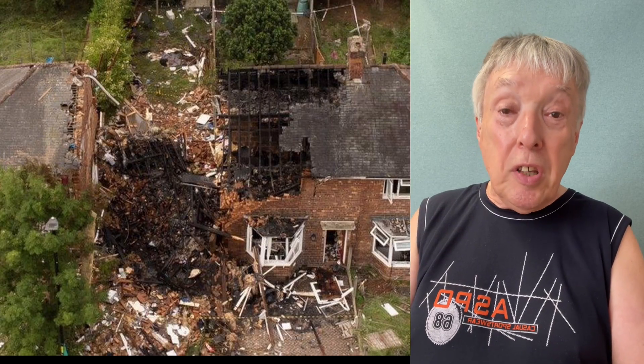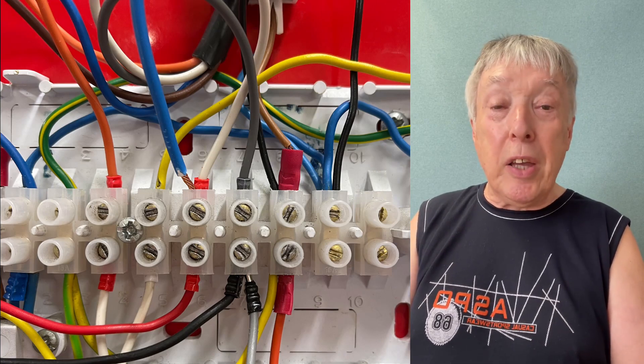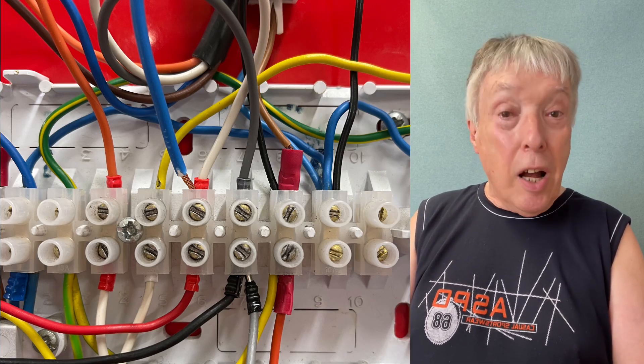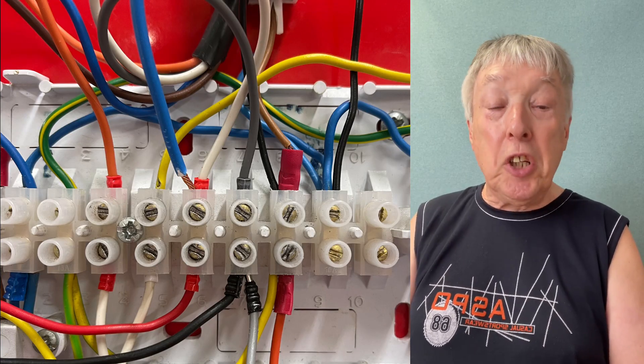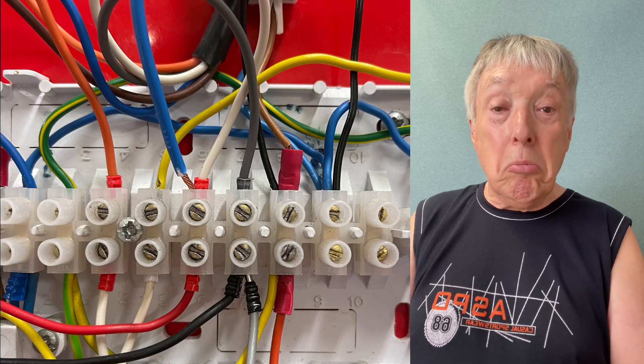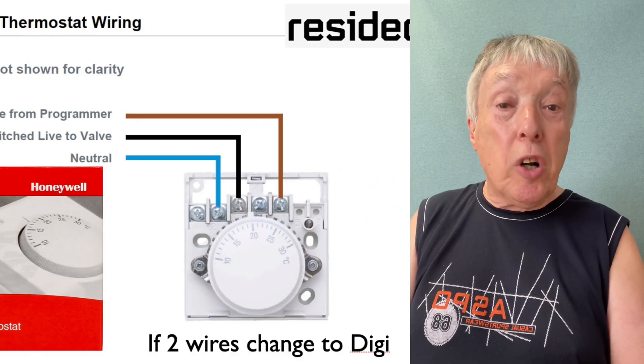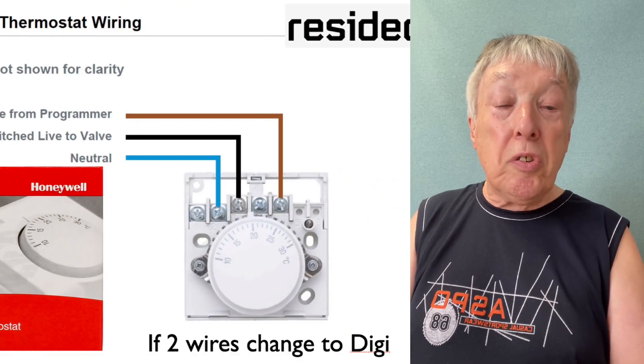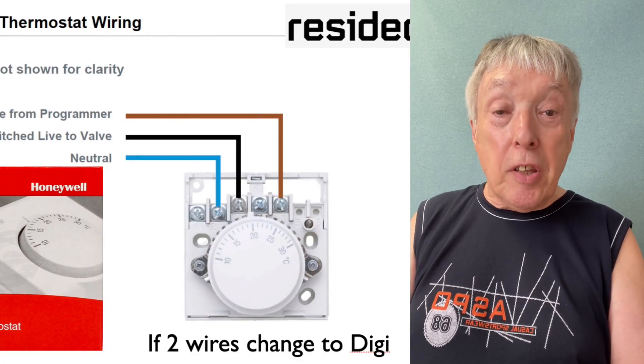Just a month or so ago I was at one particular firm having a lovely day out, and I asked those same questions over lunch with the engineers. What are you finding? They said: sloppy wiring, badly connected or not connected pipes, controls not wired up correctly, and undersized gas pipe.